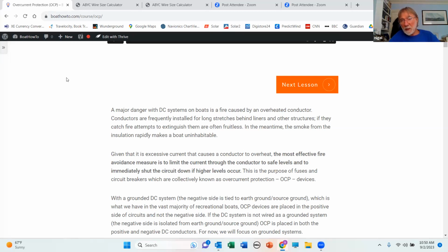output of the alternator. The problem being, if we put a fuse in that circuit close to the alternator, the heat generated by the alternator and the engine will also preheat the fuse, and it will blow prematurely. And when the fuse blows, we'll destroy the alternator. So in practice, we don't put the fuse there, but every time we do that with these super high output alternators, we're actually pushing the limits of the standards and of what we should be doing on our boats. So there are gray areas where we start to run into a little bit of trouble with some of these requirements.